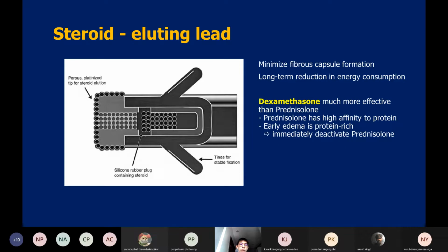Now I would like to talk about the steroid eluting lead. This is the part of the lead that would be implanted into the patient's myocardium, the tip of the lead. Nowadays, we usually put steroid into the tip of the leads to minimize fibrous formation after implantation.